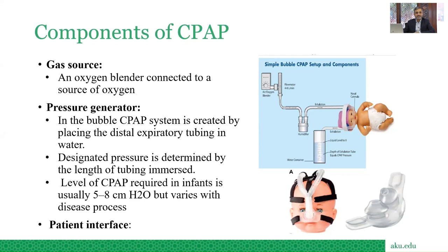So the gas source is an air oxygen blender connected to a source of oxygen, and the pressure generator is, so there are two kinds of CPAP. One is bubble CPAP. In the bubble CPAP system, the pressure is created by placing the distal expiratory tubing into the water bottle, and the designated pressure is determined by the length of tubing immersed inside the water. The level of CPAP required in infants is usually between 5 to 8 centimeters of water, but it varies with the disease process, and we can go as high as 10 or above, but usually we go up from 5 to 8. There is another type of CPAP which is delivered through the ventilator or CPAP devices, and in those cases the pressure is generated through the machine.